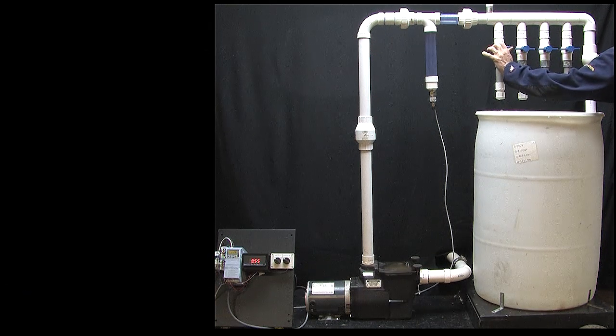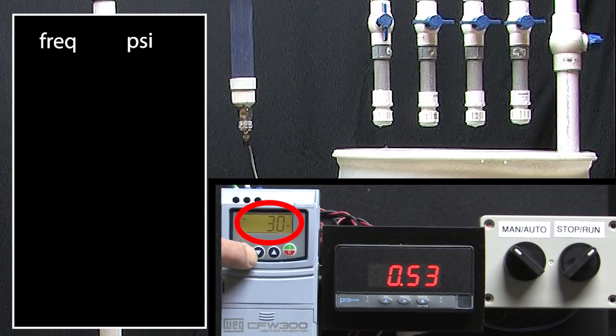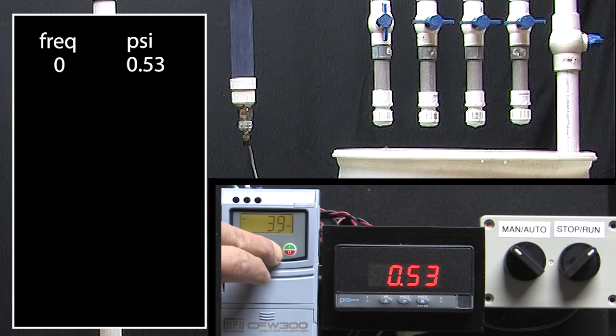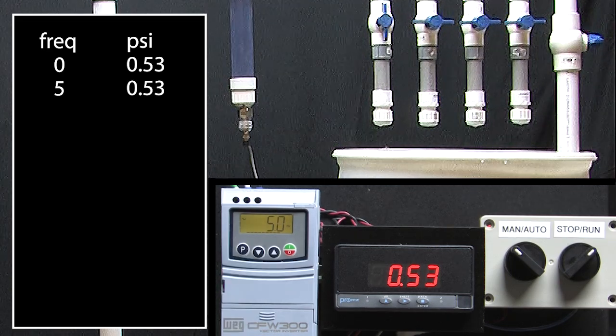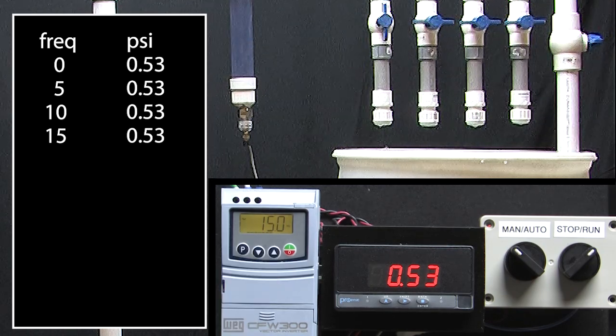With one valve open, let's switch to run mode. At 0 Hz we basically get 0 psi. No surprise there. I'll increase the drive frequency 5 Hz and we still don't have any pressure. 10 Hz? Nope. 15 Hz? Nothing.